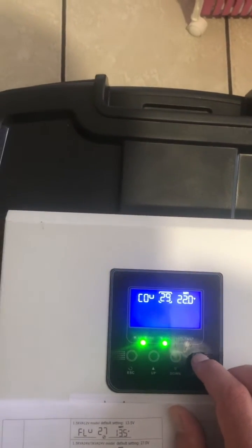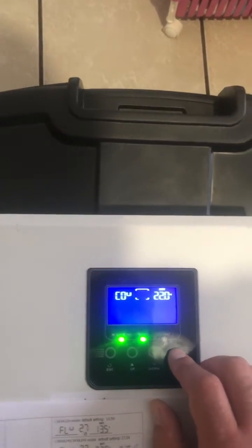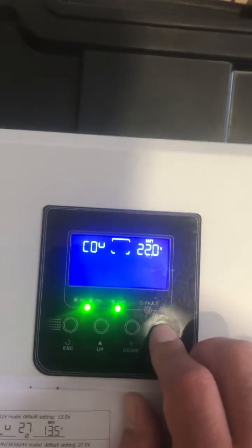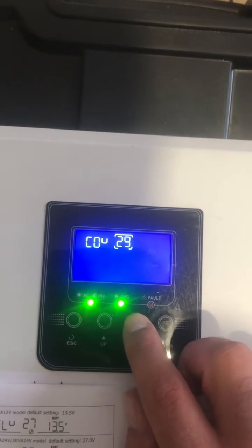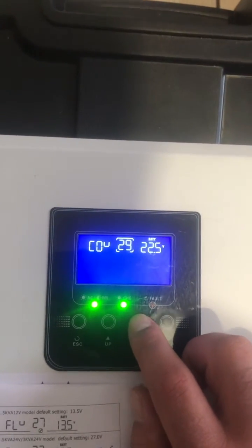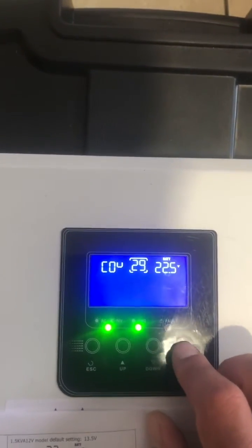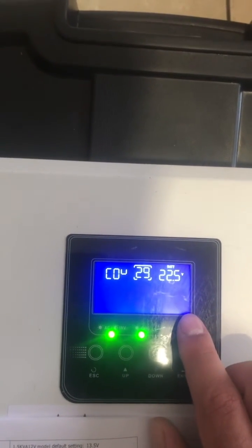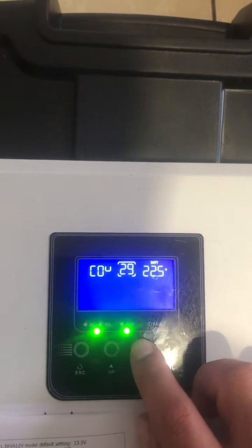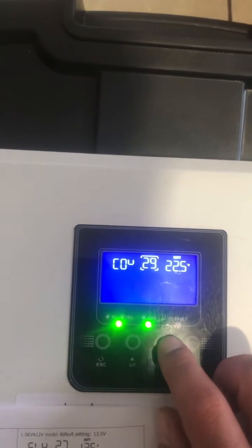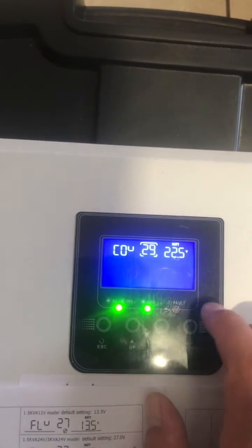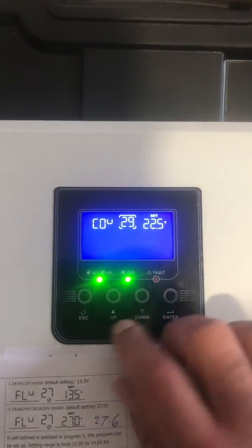We'll press enter, and here we'll set the default from 21 to 22. I like setting it to 22.5, to be honest. If you have an AGM, or a very high quality AGM battery, you can set it lower, between 21 and 22. But I like setting my batteries at 22.5 to make sure the life lasts much longer.